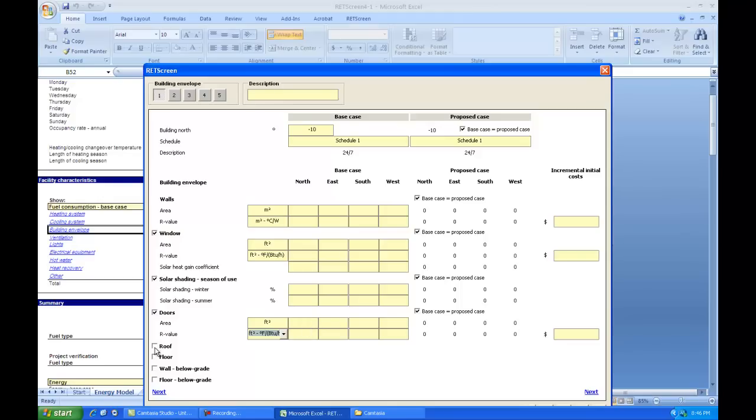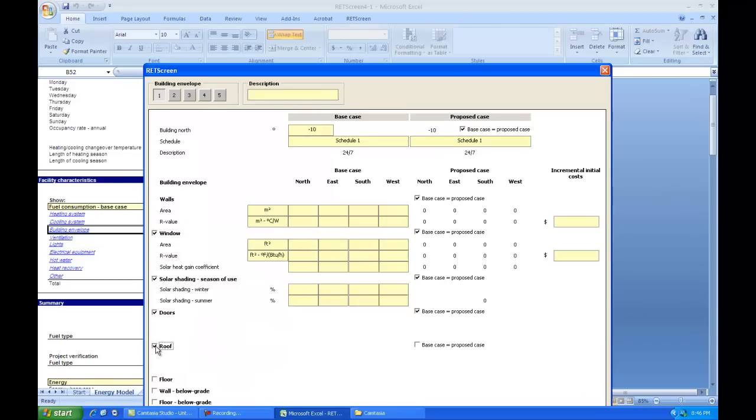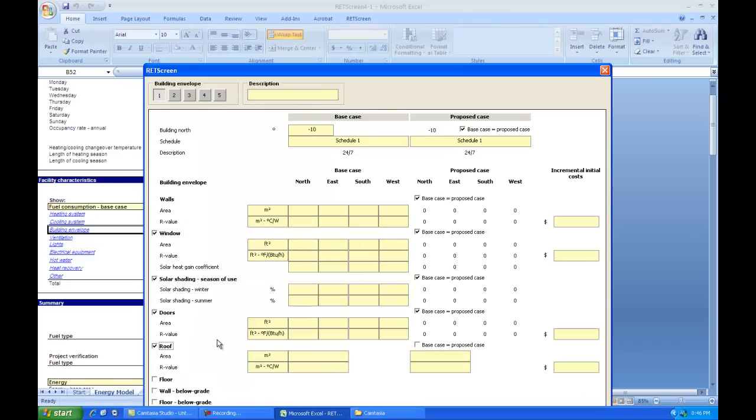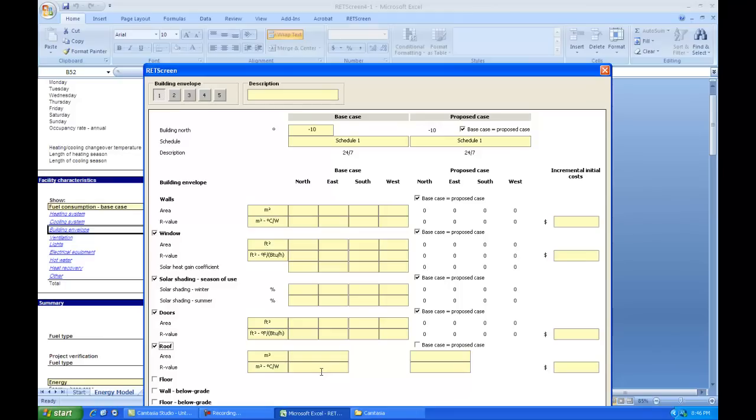The roof. This is a bit of a misnomer. What we really mean here is not the roof but the ceiling. The ceiling of the building is the area where we're going to be our thermal boundary of our building. That's where we lose heat. The roof is typically above that somewhere. And we don't concern ourselves with the roof. If we have a cathedral ceiling where the ceiling is sloping on the inside of the building and it follows the same slope as the roof, then the roof and the ceiling might be all the same thing from a thermal boundary point of view.